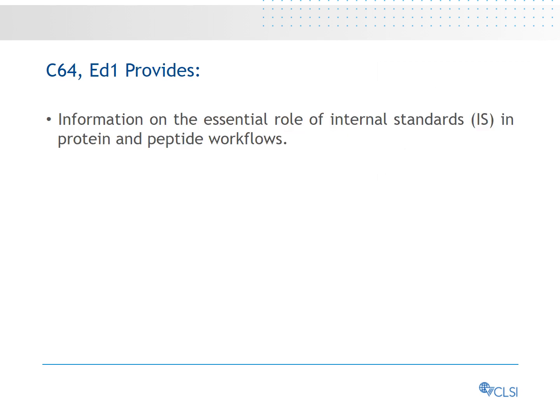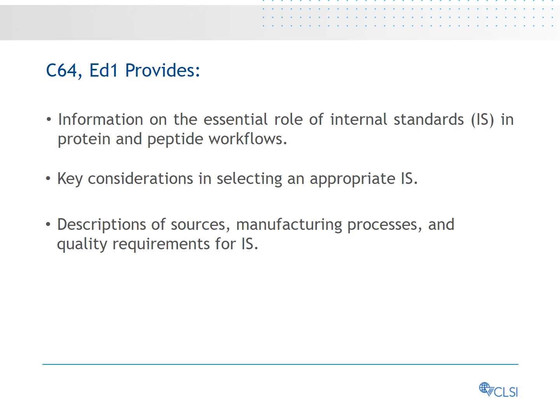Internal standards are used to control test variability arising from process variations and matrix effects between specimens and calibrators. They can be either synthetic or recombinantly expressed. Synthetic internal standard peptides are generated using solid phase chemistry, joining individual amino acids, natural or modified, in series. Expressed internal standards are proteins and peptides produced in engineered bacteria, yeasts, mammalian cell culture, or cell-free protein production systems. Sample processing requirements dictate the selection of an appropriate internal standard in a quantitative protein or peptide LC-MS assay. The test developer needs to consider the quality of the peptides with respect to chemical purity, isotopic purity, and delta mass, as well as storage.